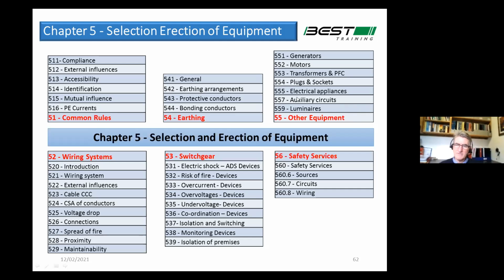Auxiliary circuits kind of relates to stuff inside motor control centers. You know, do you use low voltage ELV, or should I use mains voltage, and so on? Should I use AC or DC for the auxiliary circuits? It gives some good guidance on that. 559 then deals with luminaires, so it goes through all the various standards to do with luminaires and then some wiring methods. Unfortunately, it doesn't really address a lot of the modern approaches we take to wiring lighting using, you know, DALI, KNX, and all these technologies we now use, and lighting control modules, LCMs with multiple outlets in the one box, etc.